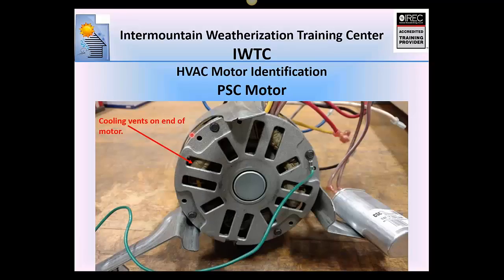Every PSC motor has cooling vents on the end of the motor — both front and back. That allows air in to cool the motor, because PSC motors produce a lot of heat by nature, which is part of what makes them inefficient. When those holes get plugged with dirt, it eliminates the motor's ability to cool itself, causing overheating, increased inefficiency, and potentially ruining the motor.